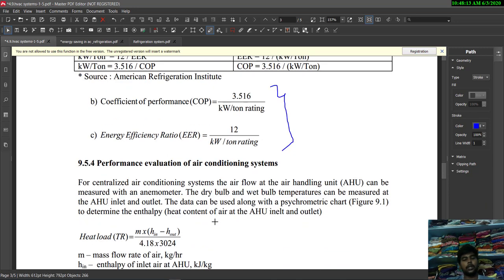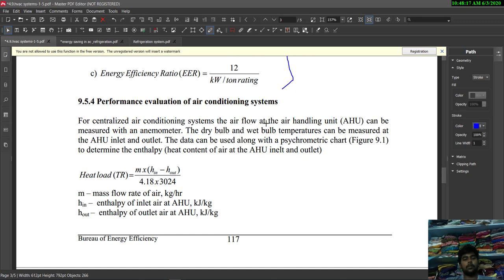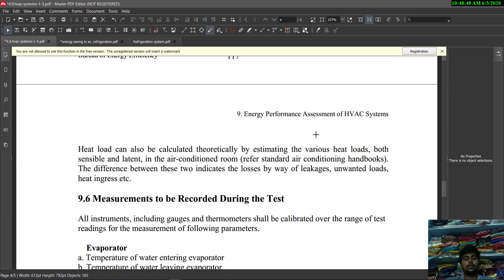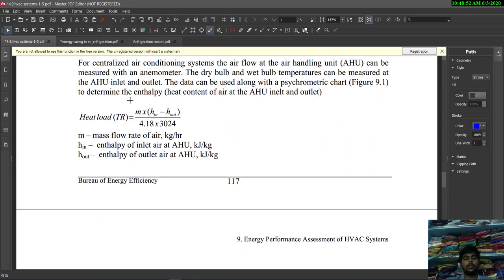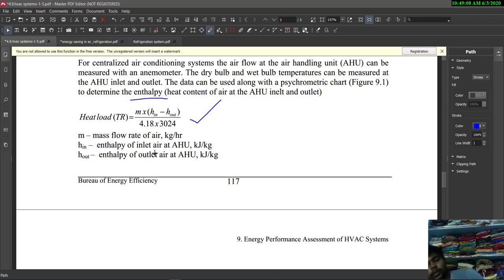For performance evaluation of a centralized air conditioning system, the air flow at the air handling unit (AHU) can be measured with an anemometer, which measures wind speed. Dry bulb and wet bulb temperatures are measured at the AHU inlet and outlet. This data is used along with the psychometric chart to determine the enthalpy content of air at the AHU inlet and outlet, with a relation involving TR, mass flow rate, and enthalpy of inlet and outlet air.